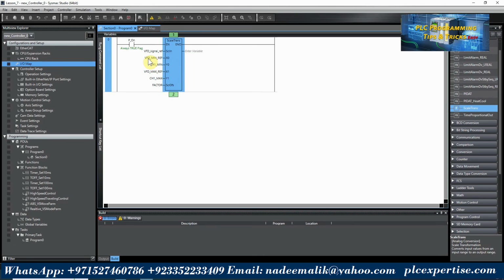This minimum and maximum speed reference, which is 0 to 50 hertz, will be converted to 0 to 4000 for the analog channel value, and these values will be sent to the analog output channel, and in return our output channel will generate 0 to 10 volts for our VFD speed reference input. So we can write here speed reference internal and data type will be real.